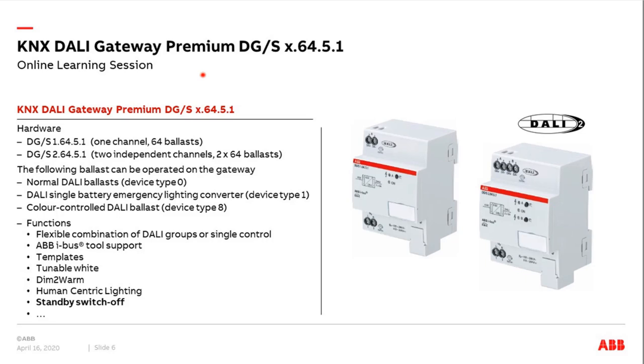At the beginning, a short overview of both DALI Gateway Premiums. Both devices are identical in functions but differ in the number of DALI outputs. The DG/S 1.64.5.1 has one channel with a maximum of 64 ballasts, and the DG/S 2.64.5.1 has two independent channels with two times 64 ballasts.